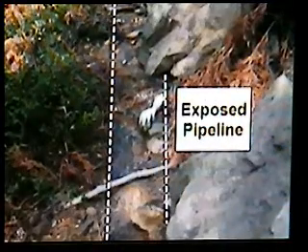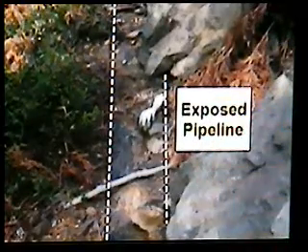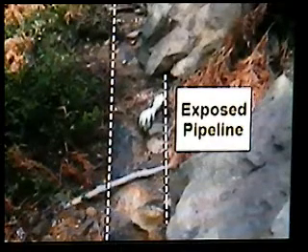Our concern with that event isn't necessarily that it would have crushed and broken that pipe. The next thing that occurs as a result of that is what we call line collapse or a vacuum. And this actually happened in Sacramento, California. What happens is that the energy of the water in that pipe continues to move, but because you get a column separation in that water, the vacuum that forms behind that water is very significant, and it actually sucks the pipe in. It literally collapses that pipe, and it can run for many miles.